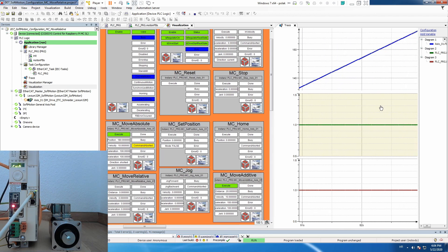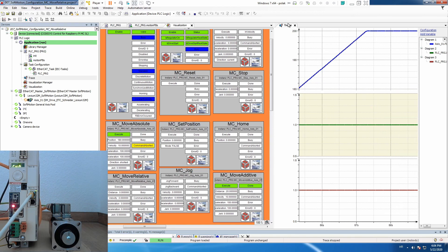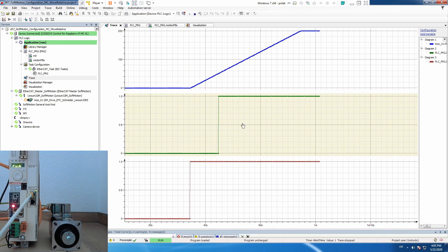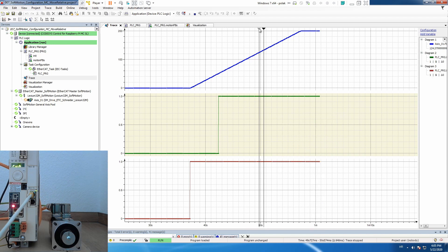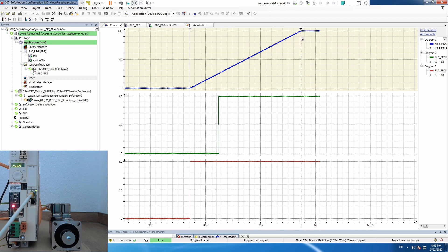It's still working — the movement is in progress. Stop. Let's stop the trace and put it across the whole screen. So what we can see: here we executed Move Absolute to 180, and then somewhere here we executed Move Additive for an additional 20. What happened is that Move Additive finished at 200. So this is the behavior of Move Additive — it adds additional distance on top of the previous movement.